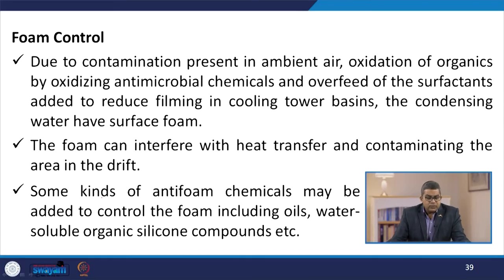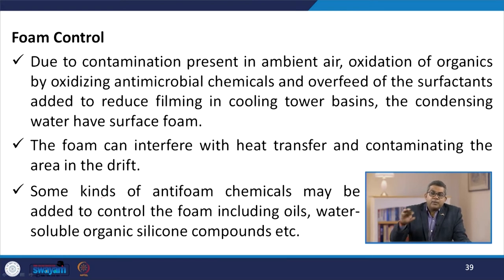Foam control: foam can arise due to contamination present in ambient air, oxidation of organics by oxidizing antimicrobial chemicals, and overfeed of surfactant added to reduce filming in the cooling tower basin. The condensing water can have surface foam that depends on the surface energy of the condensing water. This foam can interfere with heat transfer and contaminate the area in the drift. Anti-foam chemicals may be added to control the foam, including oils, water-soluble organics, silicone compounds, etc.